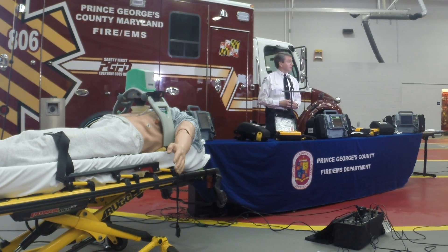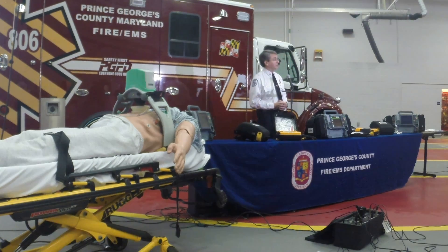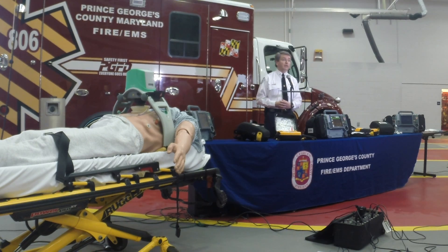Starting off with our basic ambulances, we have these automatic external defibrillators — the LifePak 1000 and PhysioControl. They offer us the newest technology available in the market, and they also offer us an option we never had before: the ability to provide pediatric defibrillation to children. The devices have the ability to hook up an energy-reducing electrode which will reduce the energy by 75%, so that it's an appropriate dose for a child from newborn to 8 years of age. Before, we did not have that ability.